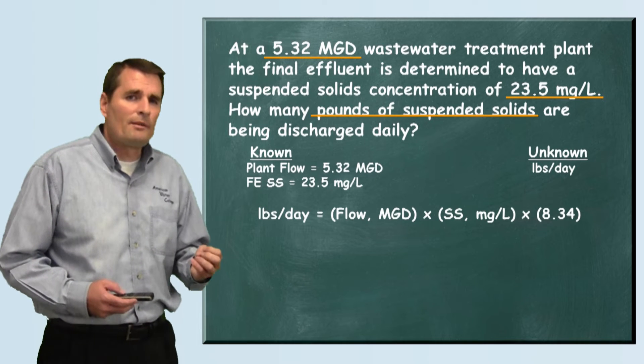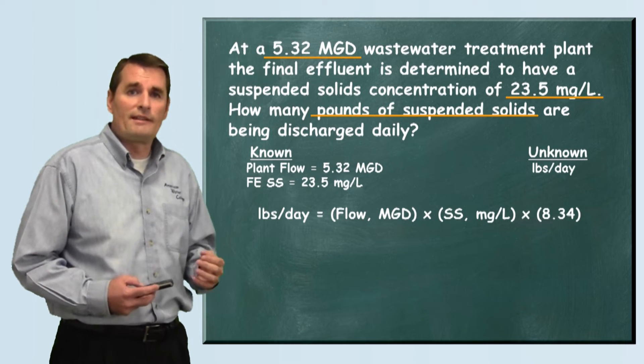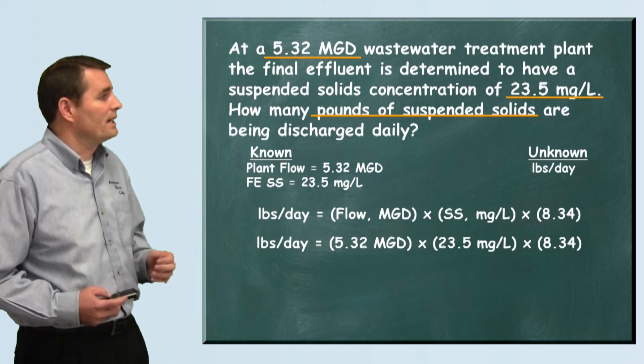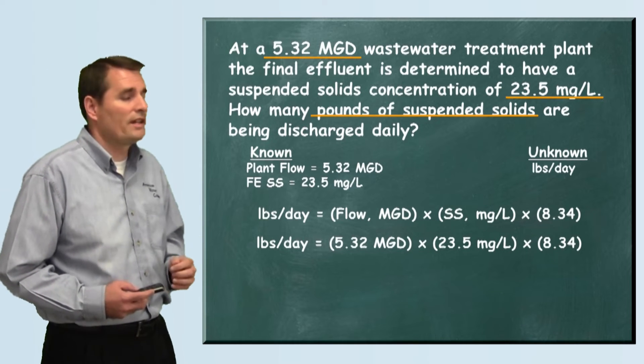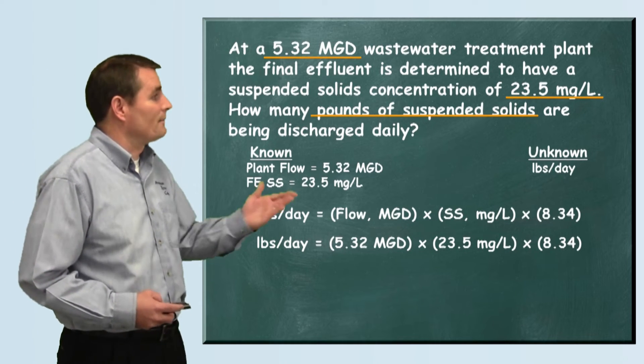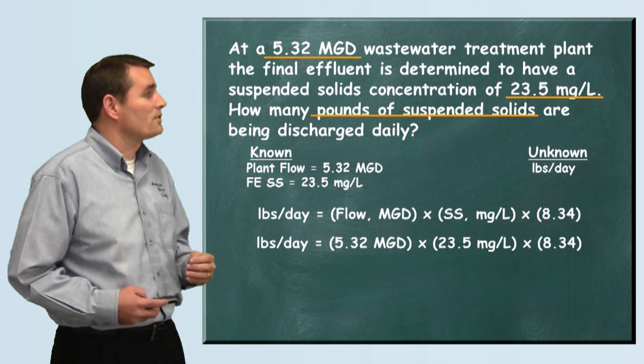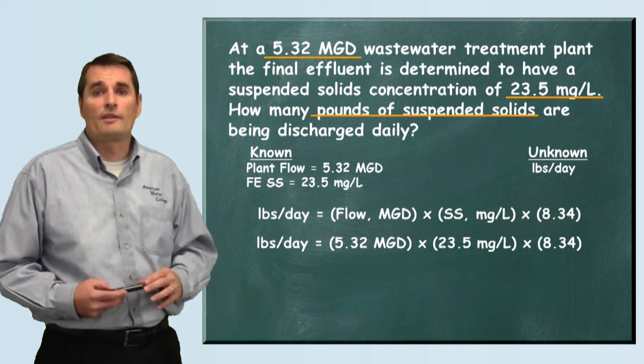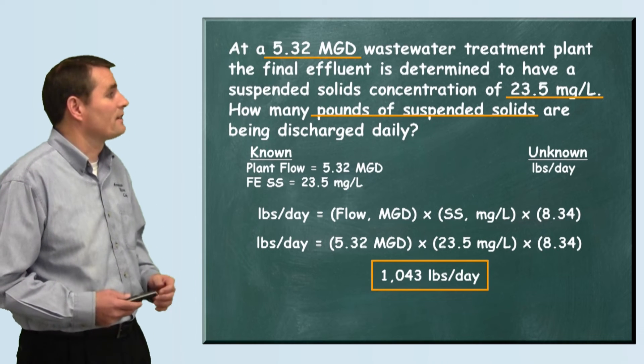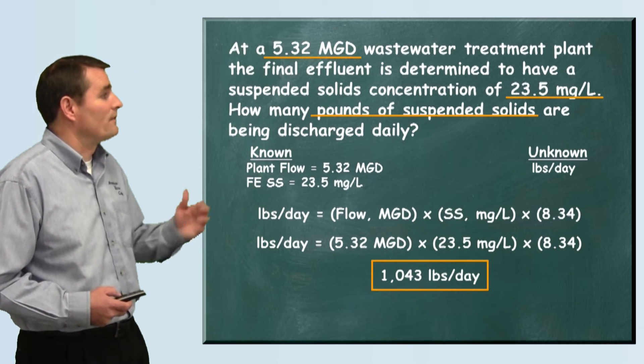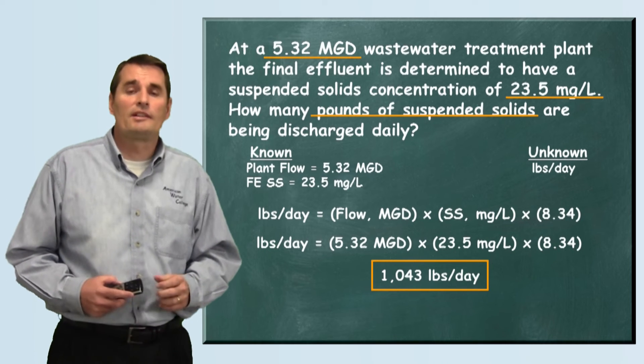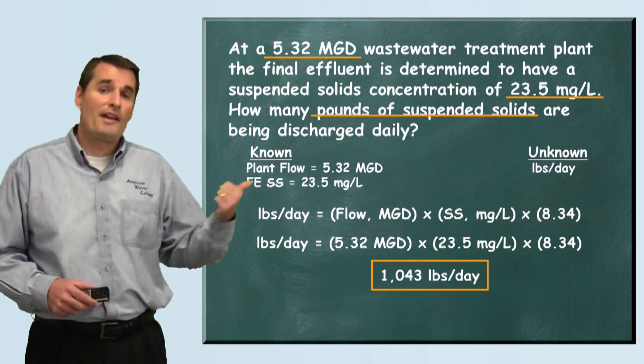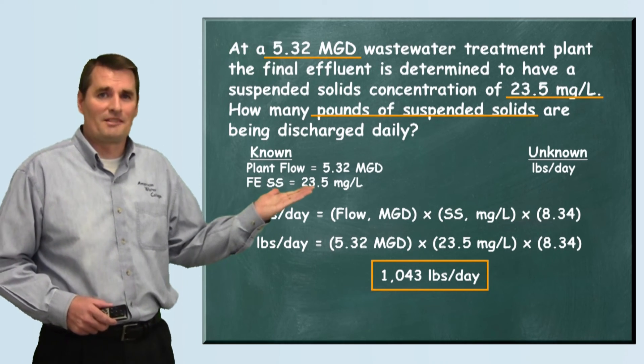Now that we've pulled the numbers out, it's simple to plug them in and do the math. Pounds per day equals 5.32 MGD times 23.5 milligrams per liter times 8.34, and when we do this math we find that we're discharging 1043 pounds per day. And that is how this problem is solved.